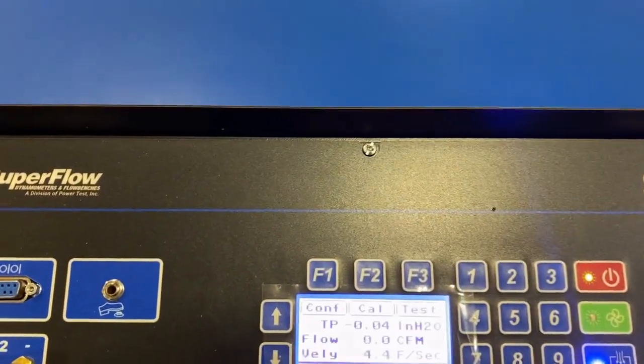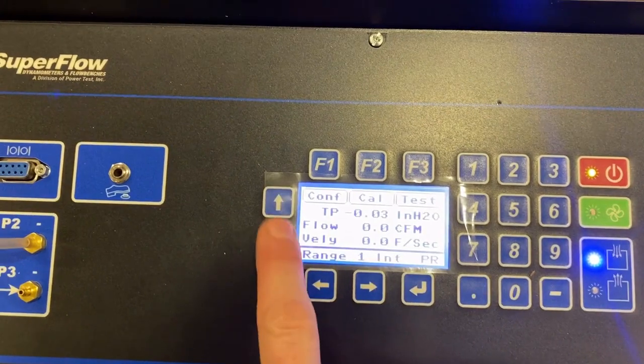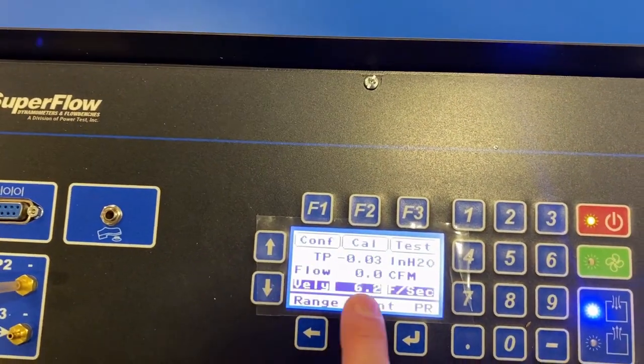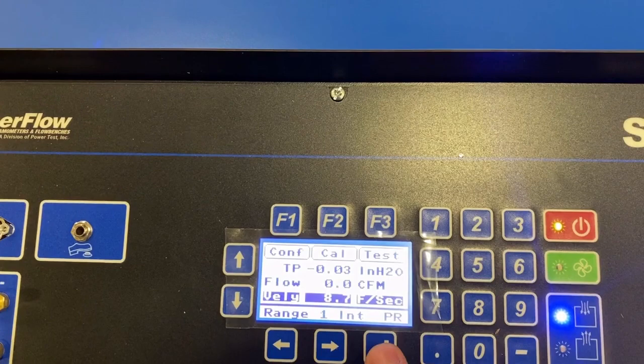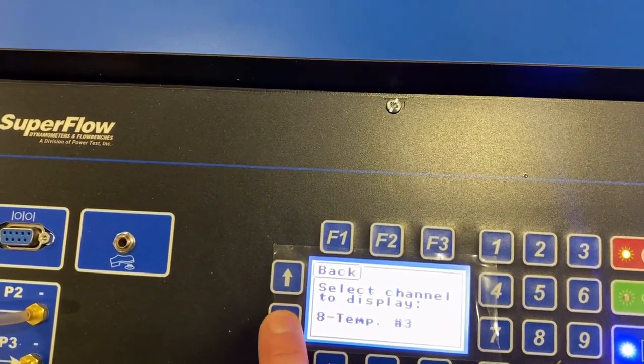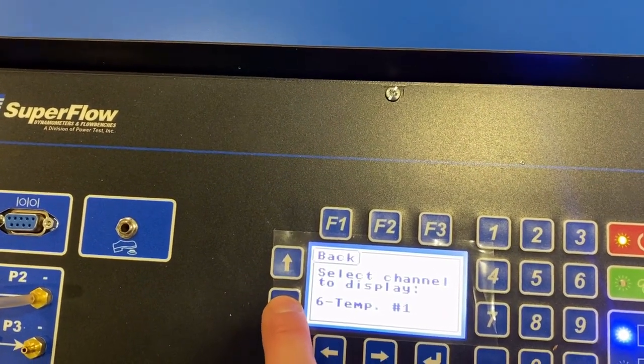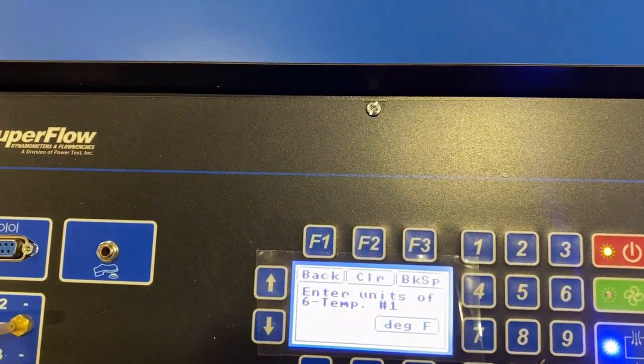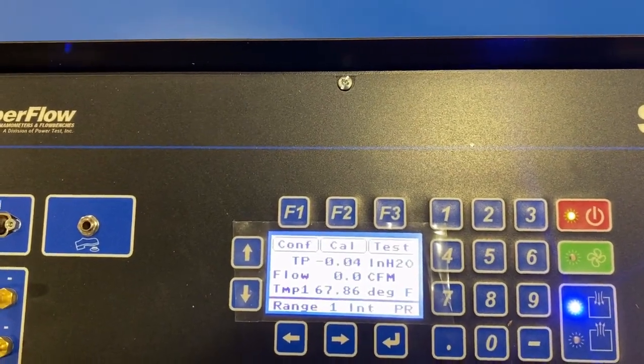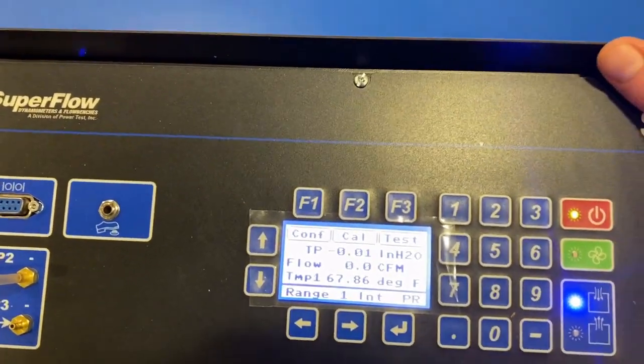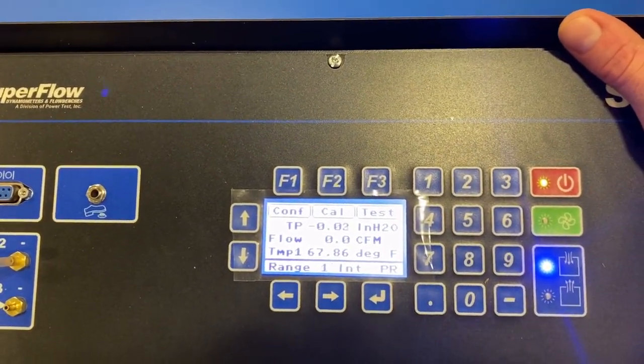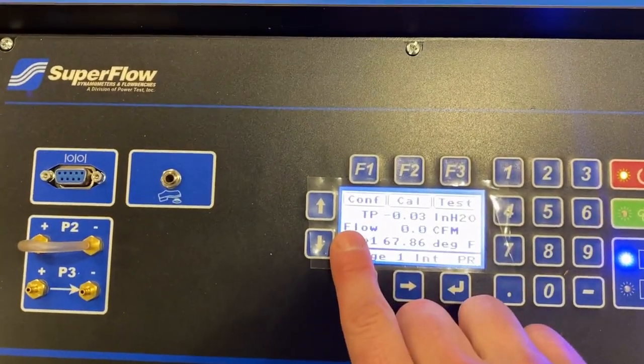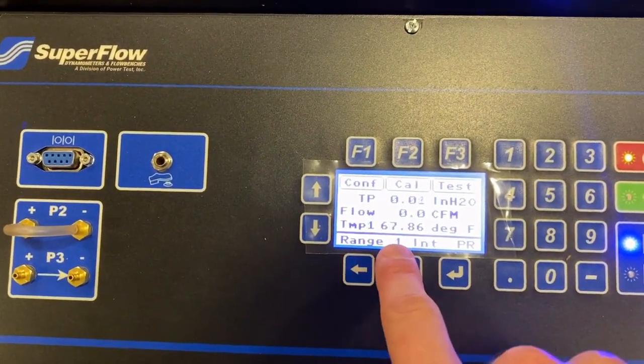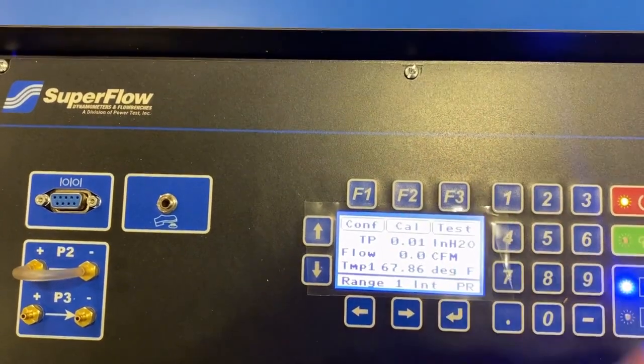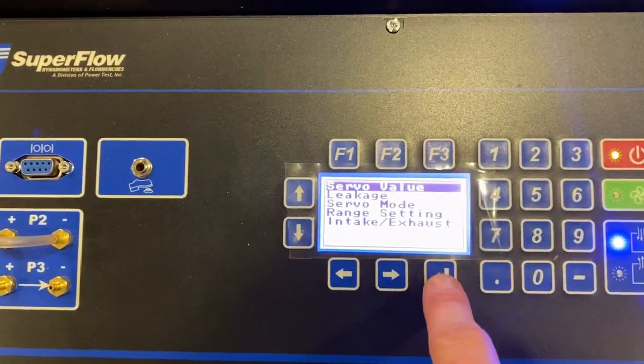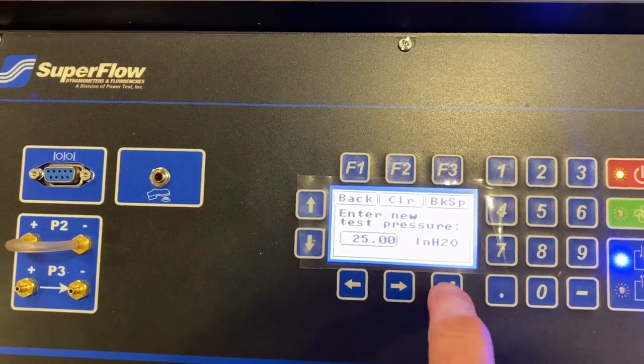We would come back into this mode. Now one thing I'm going to do is I'm going to actually change this sensor. I want to change this to temperature. Temp 1 is the temperature of the motors and the bench. We would flow this in range 1 at 25 inches of water, which we can verify. Servo value is set to 25 inches of water.